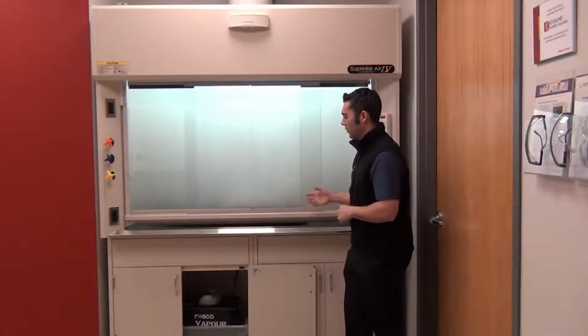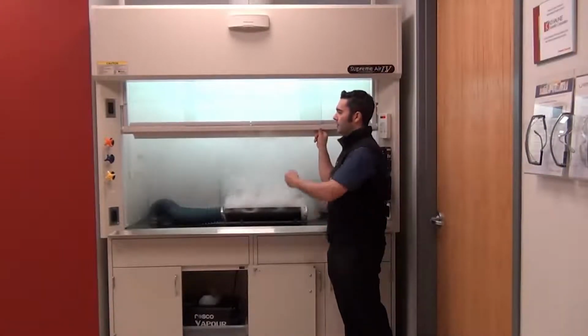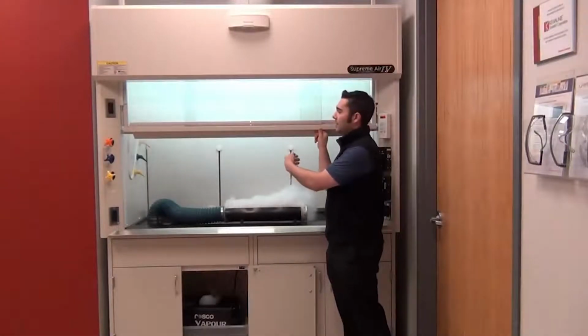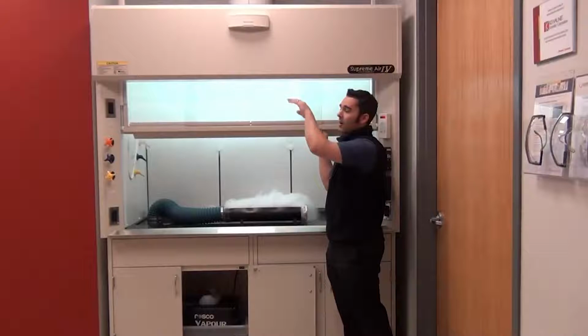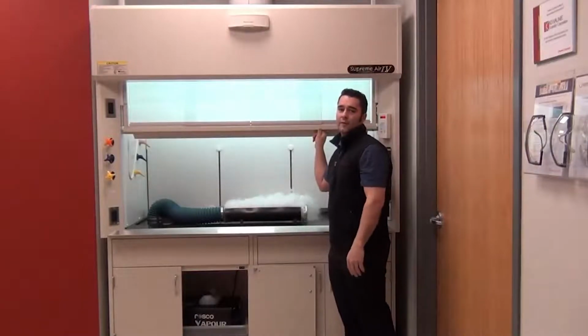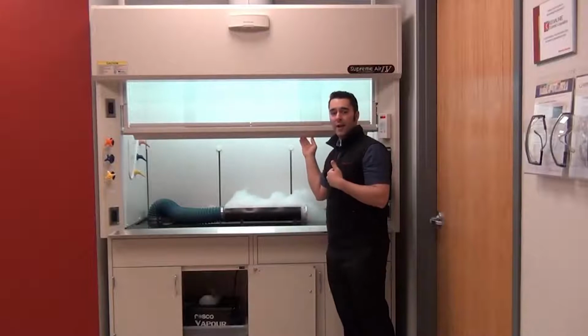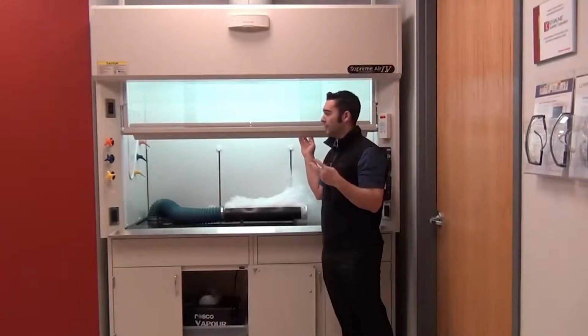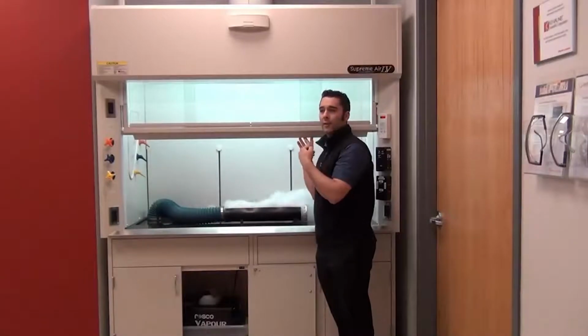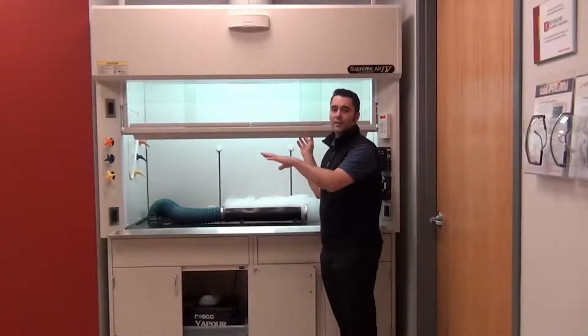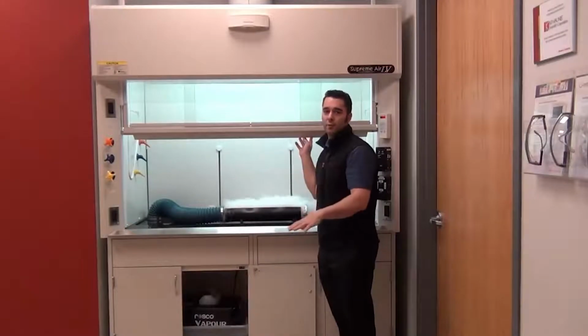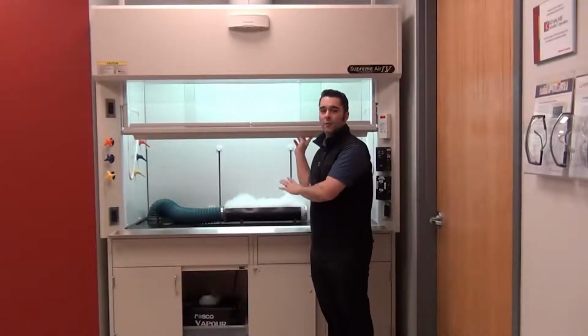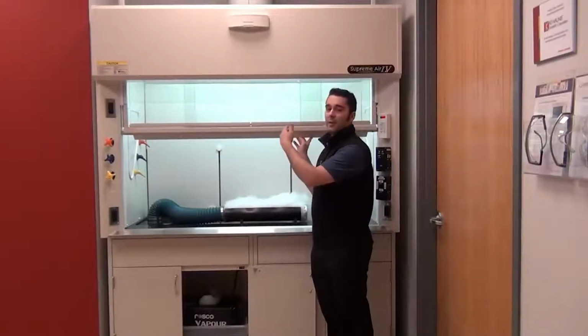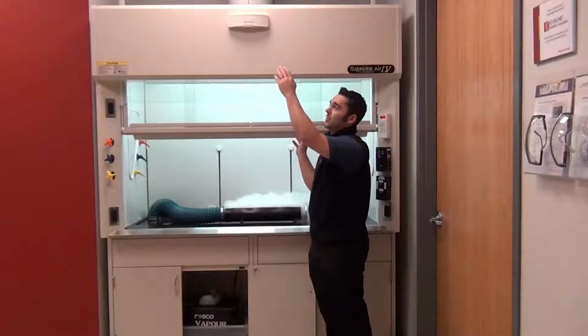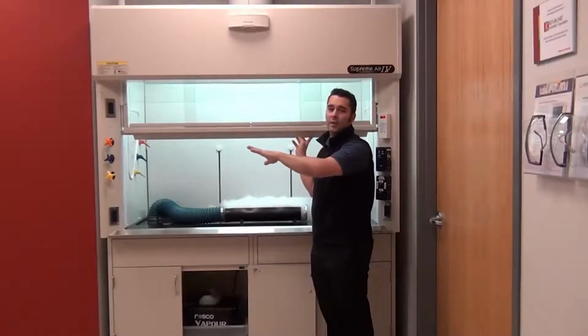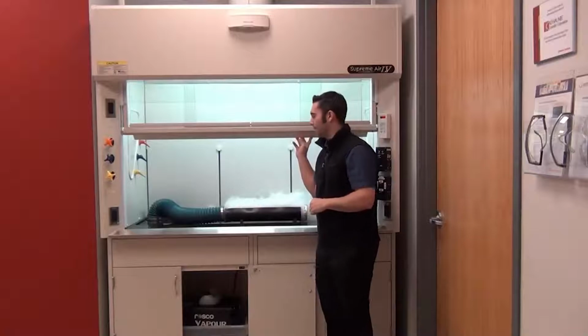So as I open this sash now, there's a lot of chemicals that are very lazily being sucked into the hood. There's also a loss of containment on top of the hood, and I'm losing containment out the front of this fume hood. So not only have I just compromised myself by having only a 3 second speed of response, because now me as the user, I'm breathing in the chemicals right here, but I'm also compromising the secondary containment zone, which is the rest of this room. Normally every chemical inside of this fume hood would be contained inside of its own hood, but now because of only having a 3 second speed of response, I'm losing containment out the top of this hood, which is contaminating the air in this room for everybody else that's breathing it.